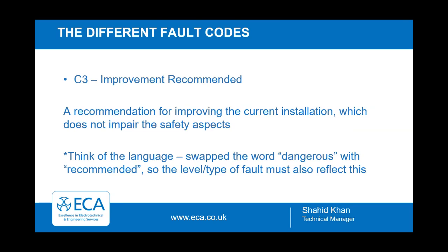If the answer is yes, then we are dealing with a C2 fault. Code C3 items are such that do not impair the safety of an installation. Think of the language that's been used. No longer do we have the word dangerous in the definition, rather it's a recommendation. The level of fault has to reflect the nature of the language used.